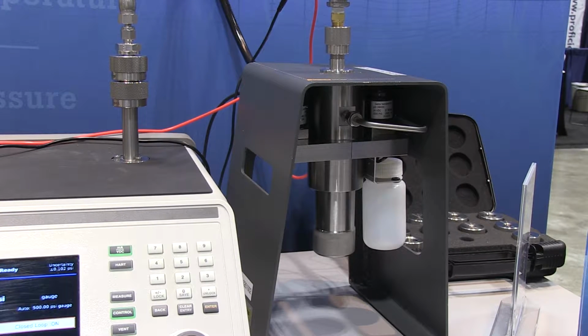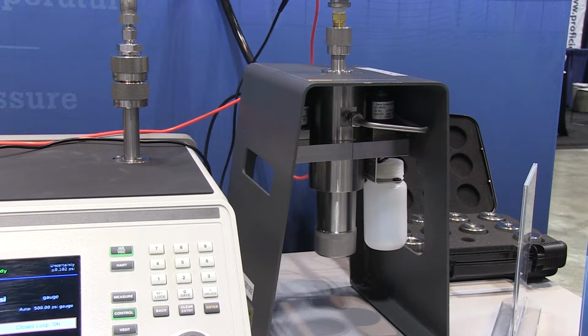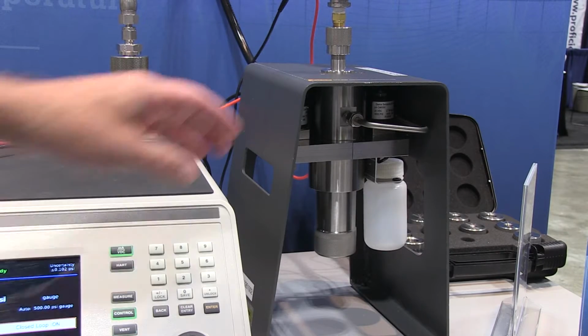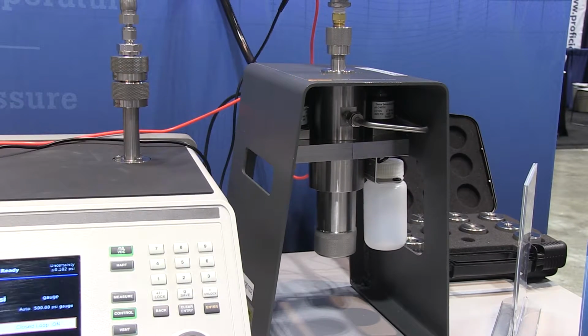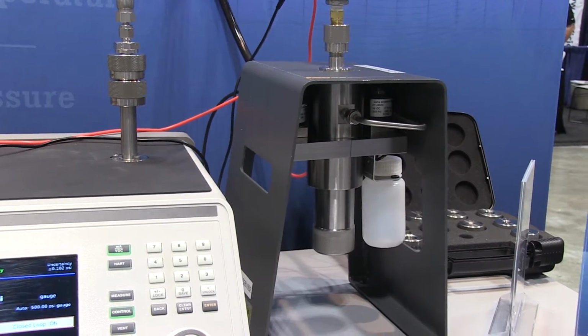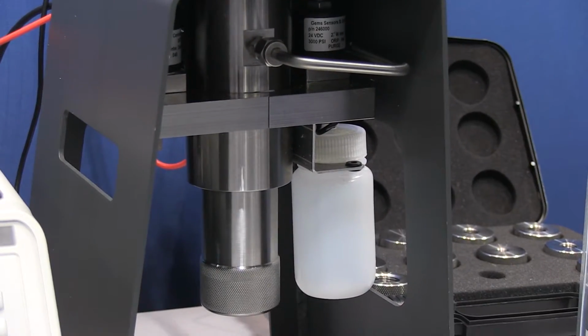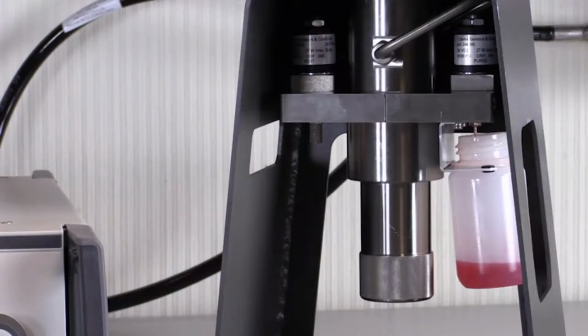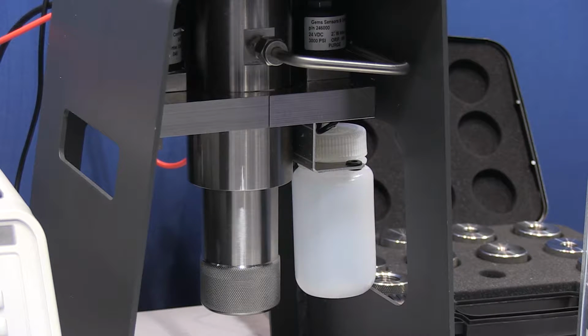So over on the right-hand side here is an accessory called CPS, or Contamination Prevention System. This was also an accessory that was released with the 6270A controller. The purpose of this is if you have devices that you know are prone to contamination, have liquids, oils, you can calibrate them with a pneumatic calibrator and be ensured that none of that contamination is going to flow back into the 2271A. So this is something you can buy at a later date, but you'll see over here it has a small vessel for the contamination, which you can purge any liquid in the CPS into this plastic bottle over on the right-hand side. The way it works is that it ensures unidirectional gas flow.